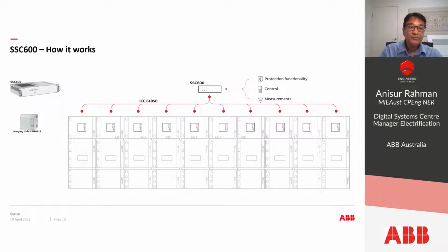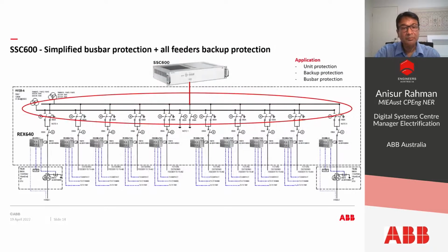So how does it work? Mainly, as you know, it only works with the merging unit. So in all bays, in each bay, we have one merging unit, and centrally the SSC 600 is here. The merging unit sends the CT/VT data through sampled values IEC 61850-9-2, and the central protection and control system SSC 600 provides the protection function, control function, measurement, and centralized monitoring system at the busbar level. So as I mentioned, we choose SSC 600 for low impedance busbar protection, and it is mainly the simplified busbar protection plus all feeders backup protection.